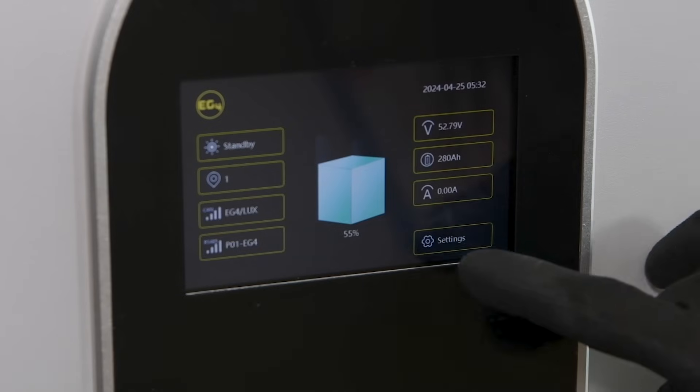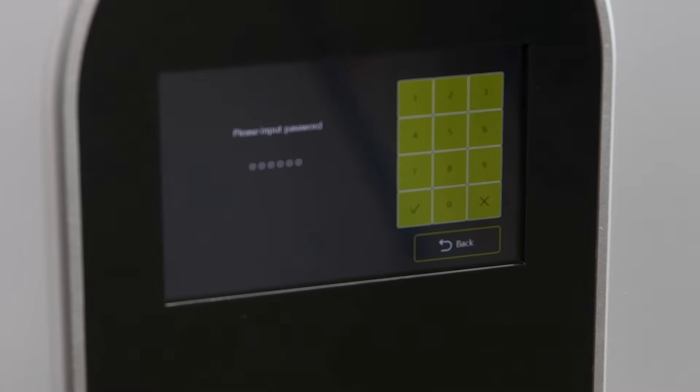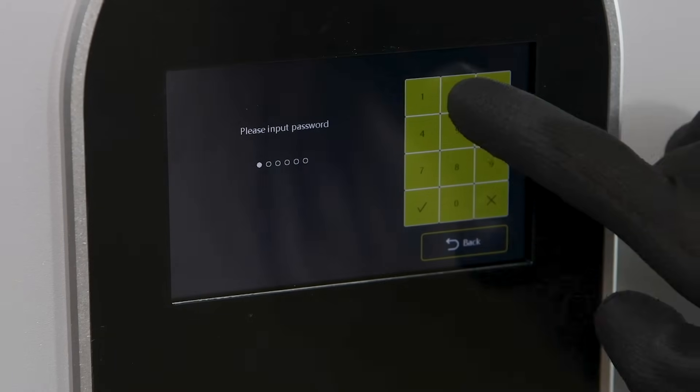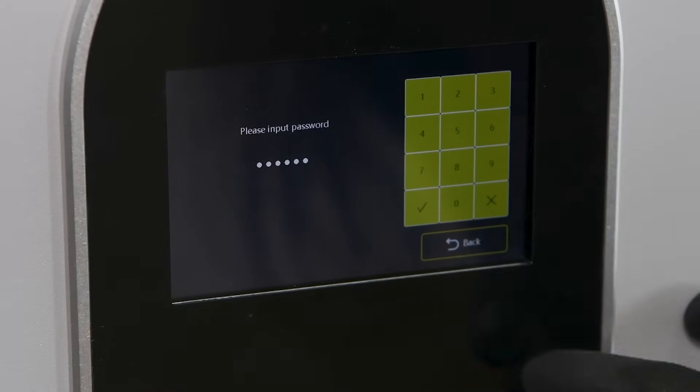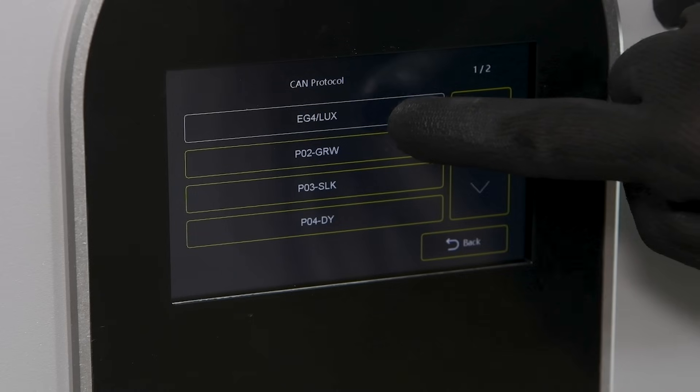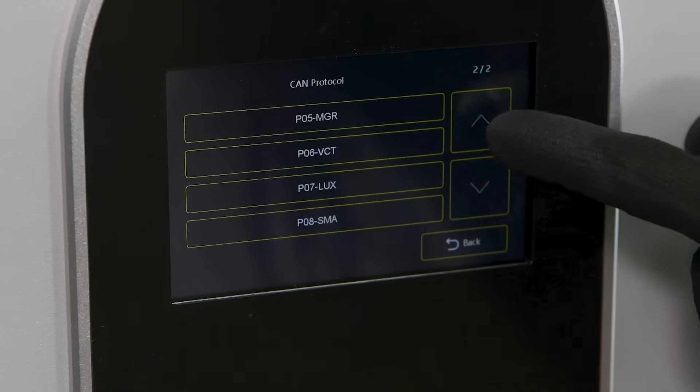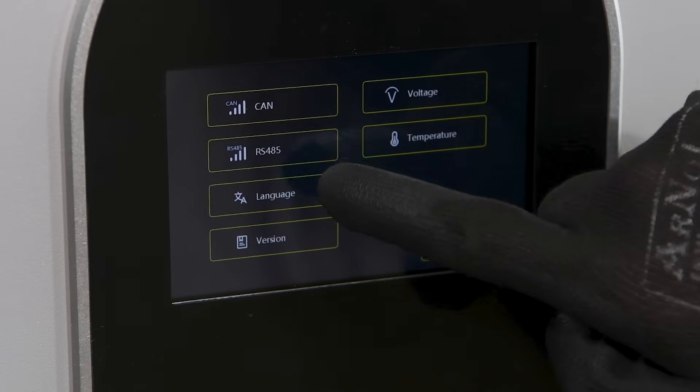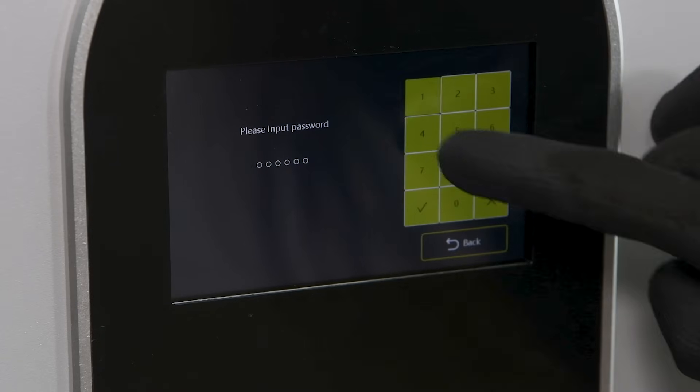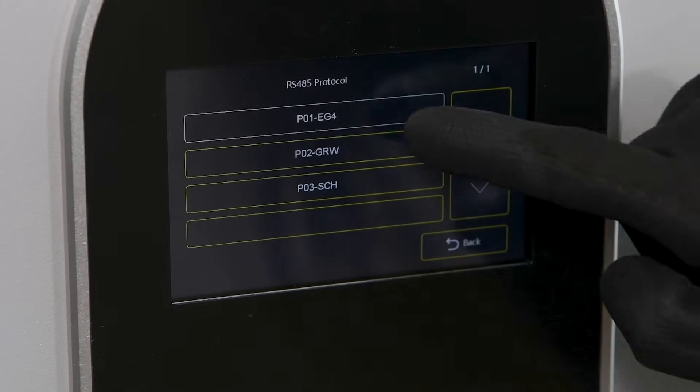If we click on the settings screen, we have a whole lot more options. We can go into the CAN settings, and the password for CAN and RS-485 is always 123456. Oh, there's our protocol. We have a 6000 XP, which is the EG4 Luxe, so we'll select EG4 Luxe, but you can see we have many more. We can scroll up or down. We'll click back. If we wanted to set RS-485, we could set that here, and again, the password would be 123456. Hit the check mark, and again, we have EG4, Growatt, or Schneider. We have EG4, so we would select that and click the back arrow.